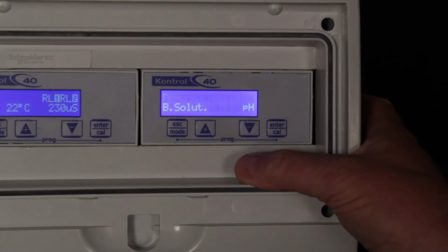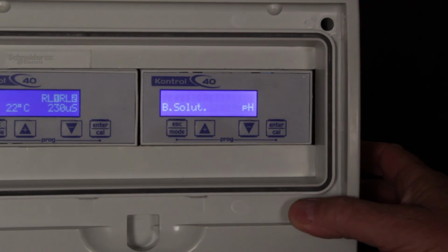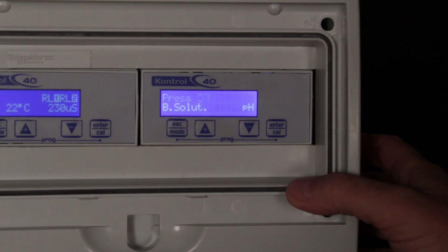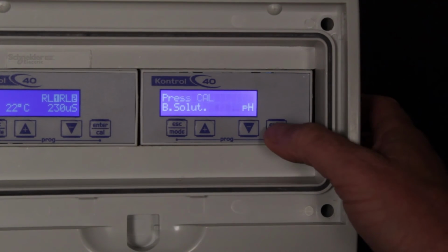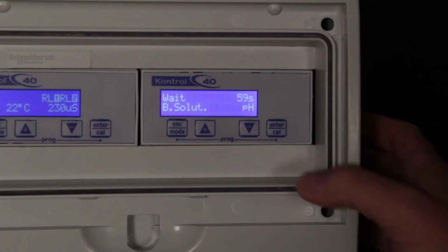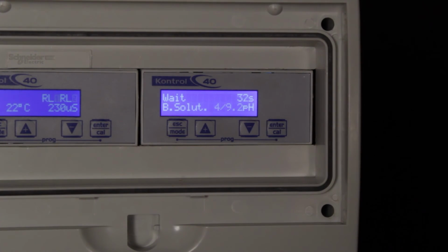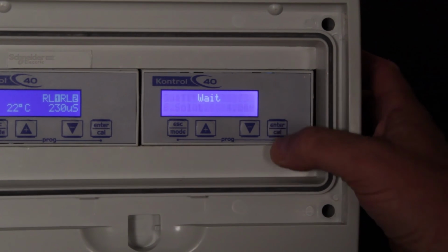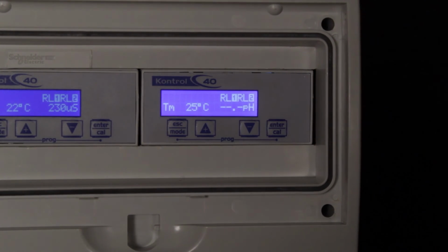It indicates now either a 4 pH or a 9.2 pH buffer. Press enter again and the timer will start to count down from 60 seconds. At 30 seconds, the controller will detect what buffer you are using, in this case a 4 pH buffer. The controller once again gives you a quality value of 75% in this case, indicating that we are still within spec. Now press enter and you have successfully calibrated the pH probe.